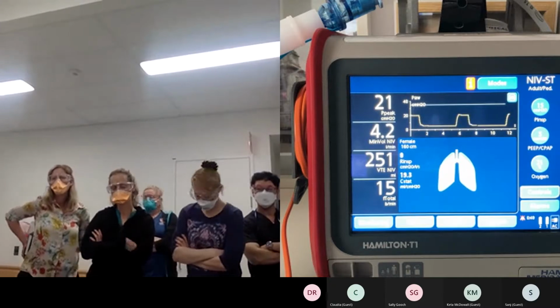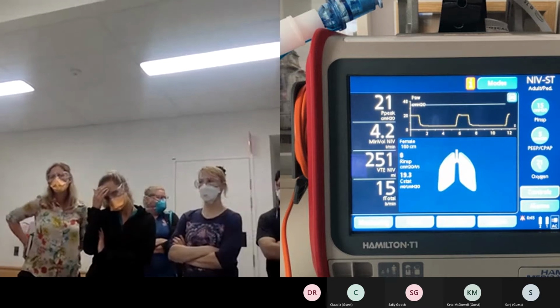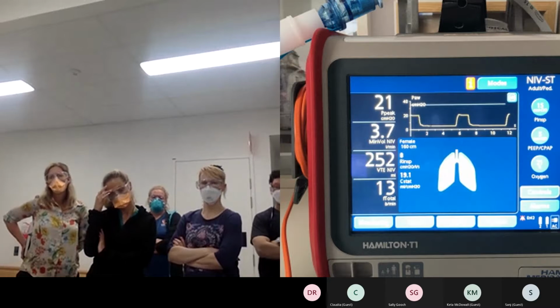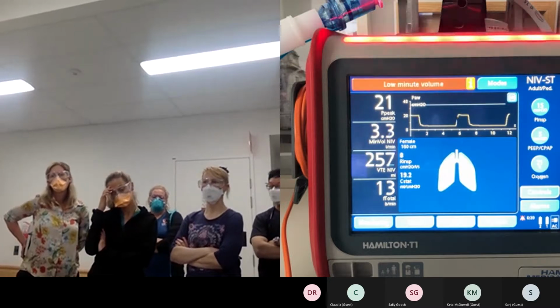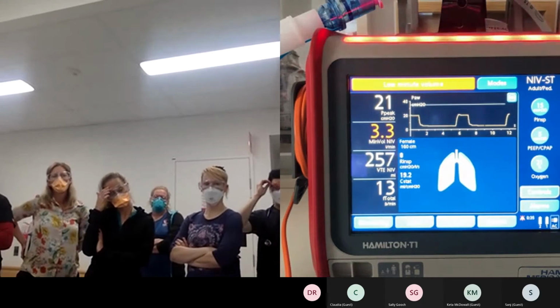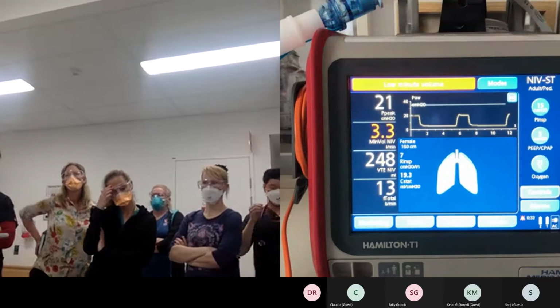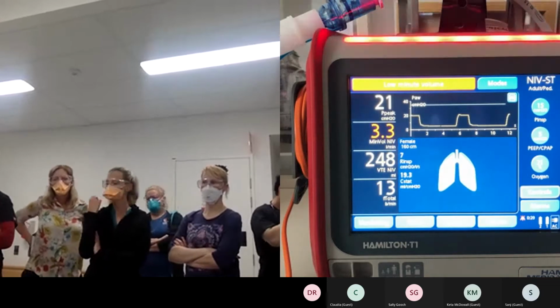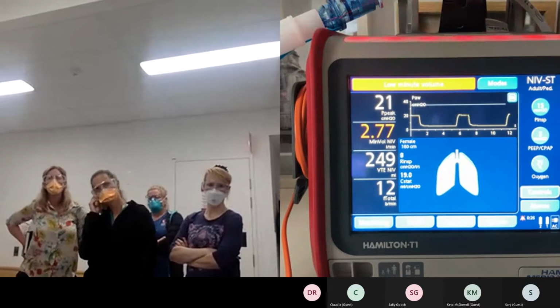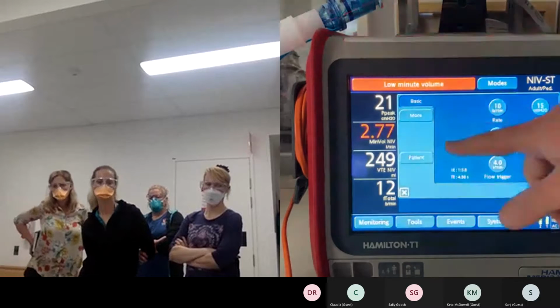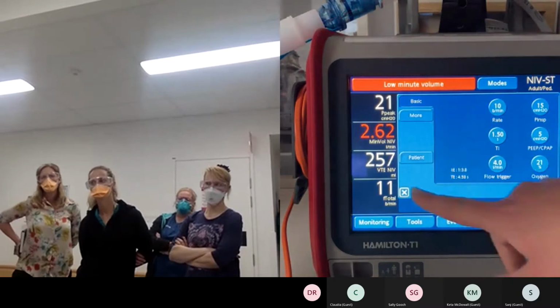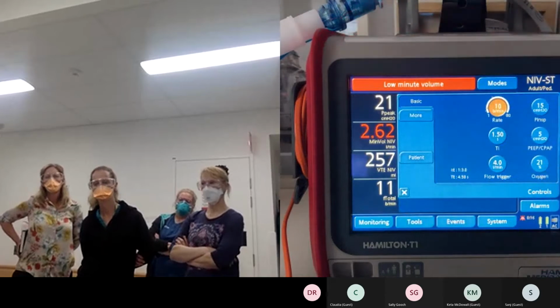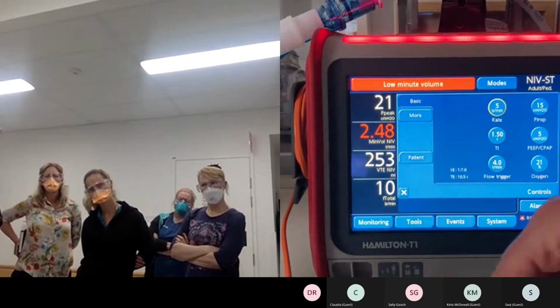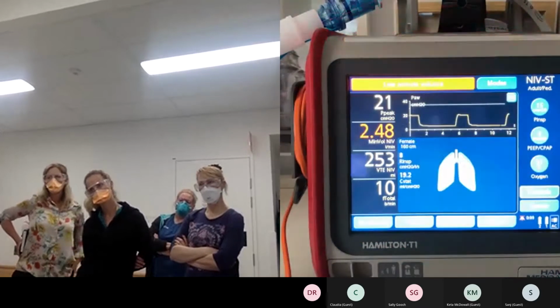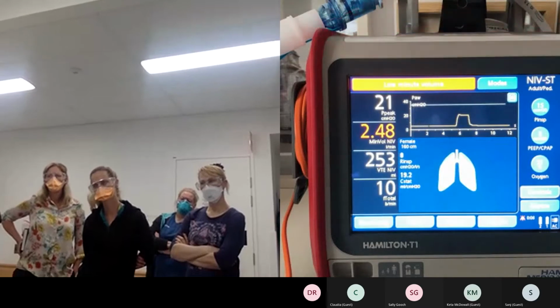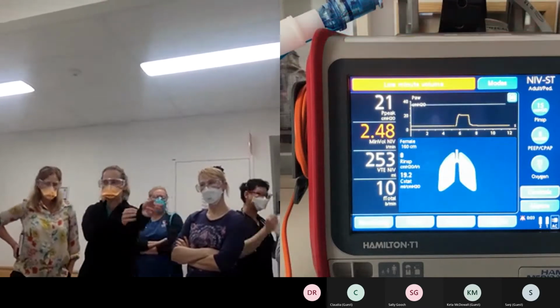So this is where people will often use the ST mode more for pre-intubation, if they've got that deteriorating patient, or for palliation. What does ST stand for? Just a question. Spontaneous time cycled. So it is synchronized. If your patient is breathing, it will synchronize to their efforts. But when you look in controls, you no longer have that apnea backup because you've set that rate. It's also important to be mindful that it does have a minimum rate of 5. So don't set it at 5. But that's about it.